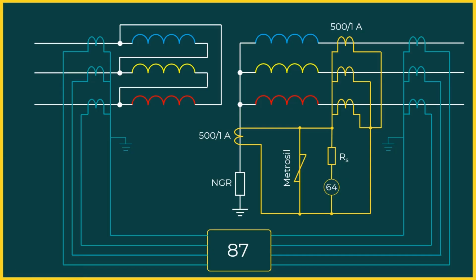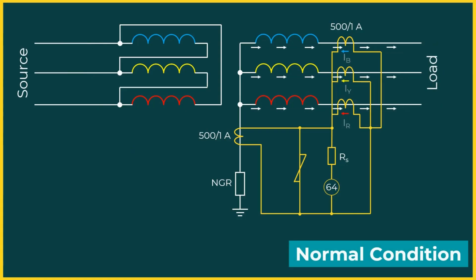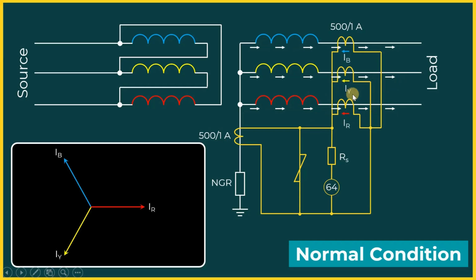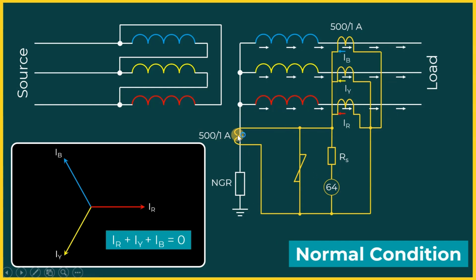To understand REF operation clearly, let us look at three conditions. First, we will start with the normal load condition. Imagine this transformer is feeding power to a three-phase balanced load, and these white arrows represent the load current flowing through the transformer winding. The current through the phase CTs will be balanced and 120 degrees apart, so the vector sum will be 0. Since there is no earth fault current, there is no current through the neutral CT. Therefore, there is no imbalance current which can flow through the REF protection relay.